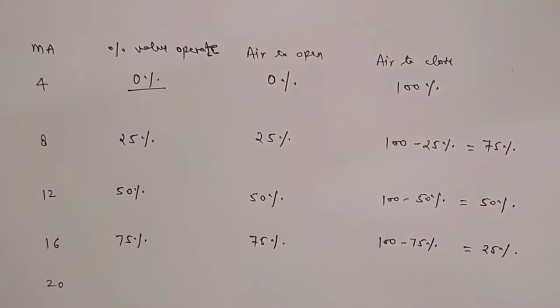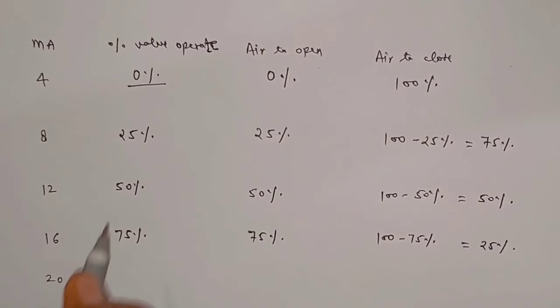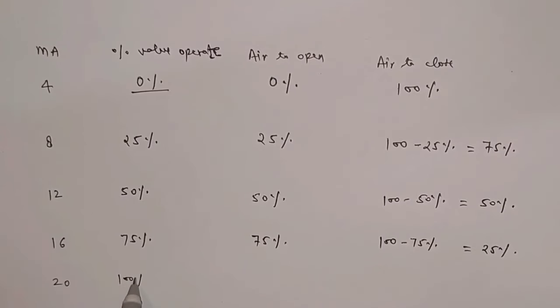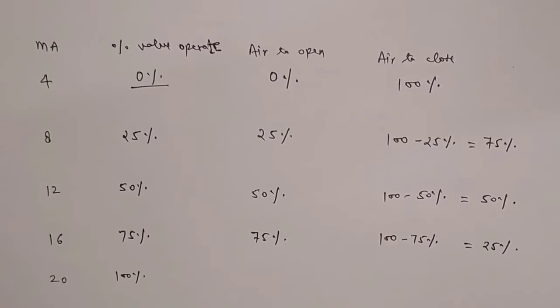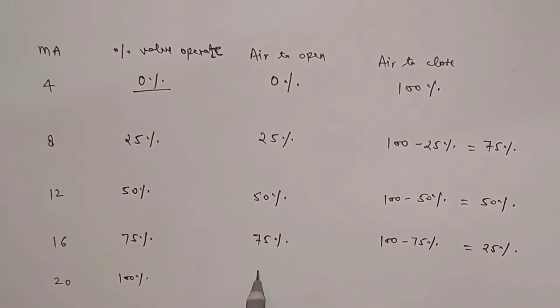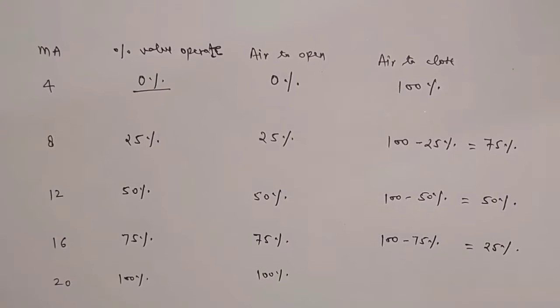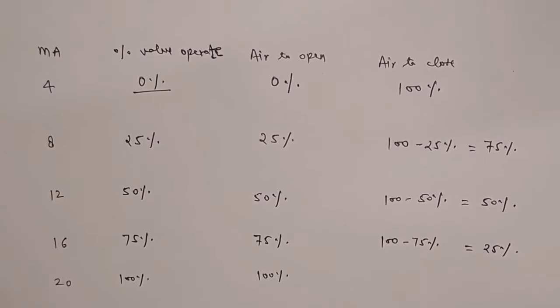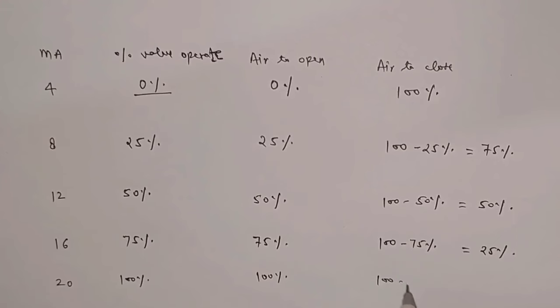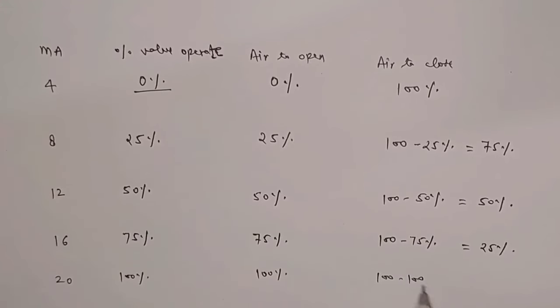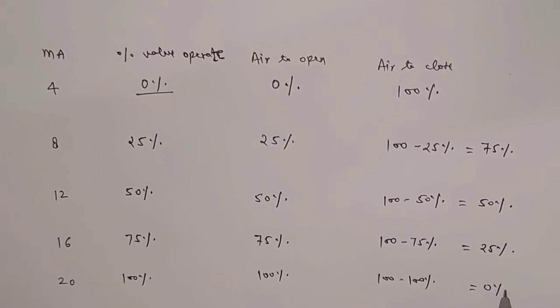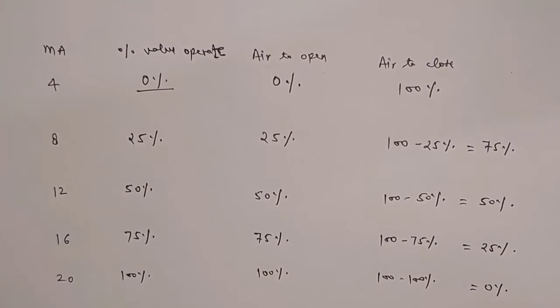Similarly, at 20 milliampere signal, it will be 100%. So the opening percentage of the air-to-open control valve is 100%. And the air-to-close control valve opening will be 100 minus 100%, meaning 0%.